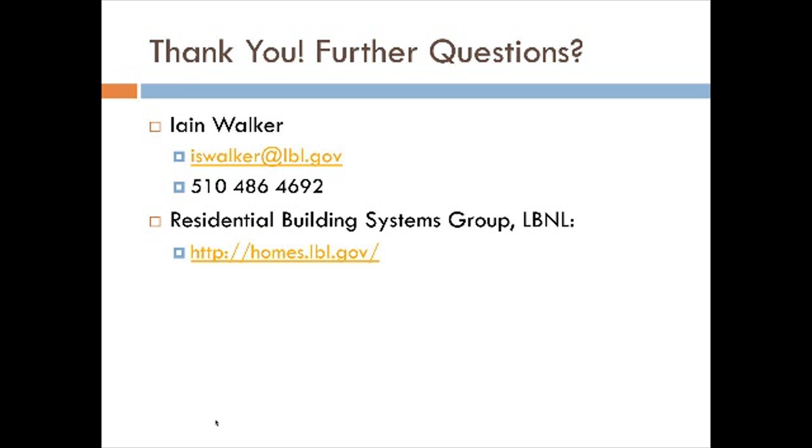I mean, the theory sounds great, right? The theory is that if you have a bunch of really good detectors that tell you there's almost no pollutants in the house today, so you don't need very much ventilation, you can see why that's attractive, right? You can see some significant energy benefits there. And the other side of that coin is, if they see that pollutants are high, they could go, we better turn up the ventilation a lot right now, and then you can see the IAQ benefits. That's an ideal. We're just a long way from it, and it's mostly due to cost, and the sensors simply are not robust and reliable enough to be used in that way yet.